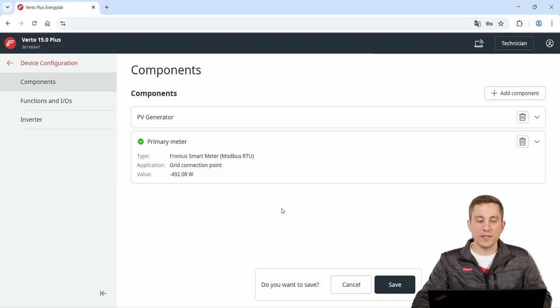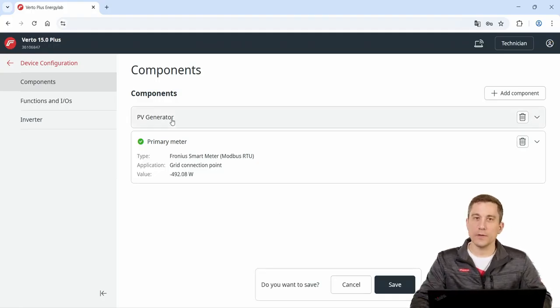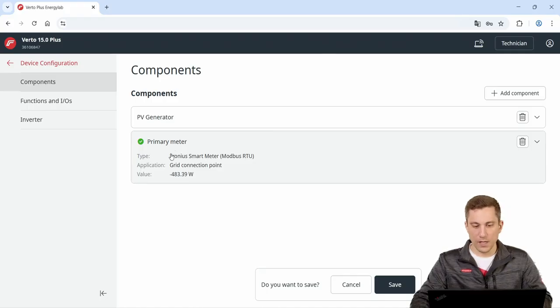For the hybrid system, you need to have at minimum a PV generator. There you are setting in the settings for the PV modules that you installed on the roof. And you need to have a primary meter so that the hybrid system can control itself. In the primary meter, you can either set a Modbus RTU, TCP or MQTT meter, depending on which smart meter you are adding. After that, you click on Add Component and then you choose the battery.